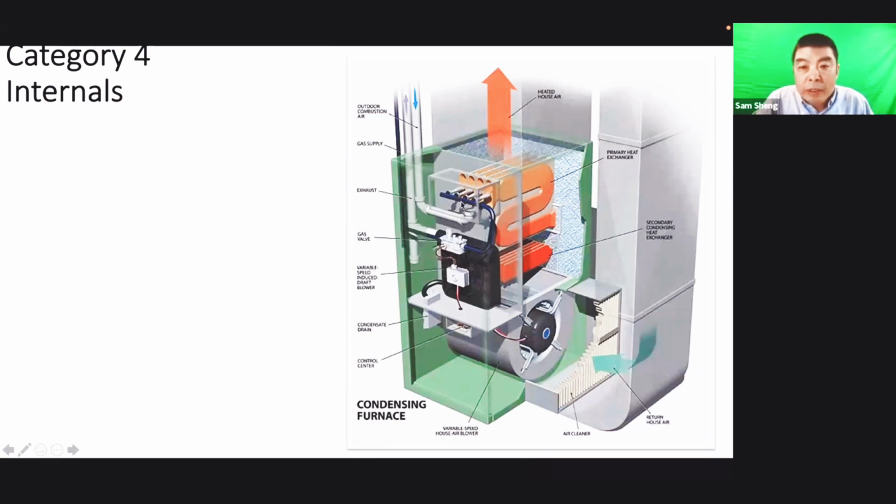Okay, you see this burner is a new style. It's shorter than the category 1 burners. The category 1 burner goes from here to inside here, so that's easy to collect dirt, and it needs to be serviced every year. But with this one, normally the burner orifice is not clogged.